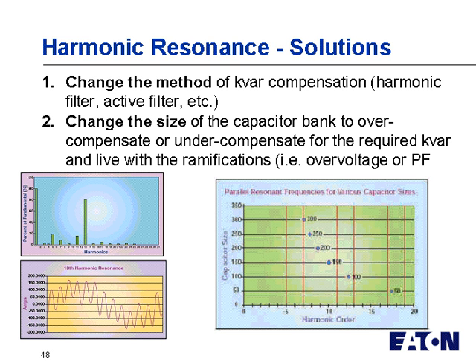Now, how do you solve that problem? Well, there's really two methods. One is you change the method of kVAR compensation by applying, for example, a harmonic filter or an active filter instead of a straight capacitor. Or you can change the physical size or the electrical size of the capacitor bank to overcompensate or undercompensate for the required kVAR. But you have to live with the ramifications. For example, you may have additional overvoltage if you put too big of a capacitor on, or you may still have a power factor penalty if you don't put big enough capacitor on. So you may eliminate most of your penalty, and you may not eliminate all of it if you put a smaller capacitor on.